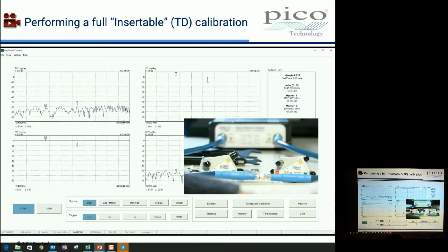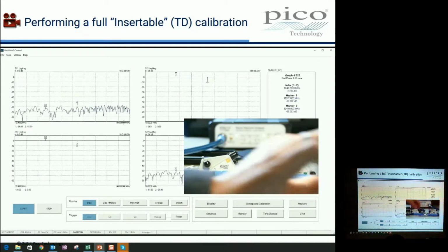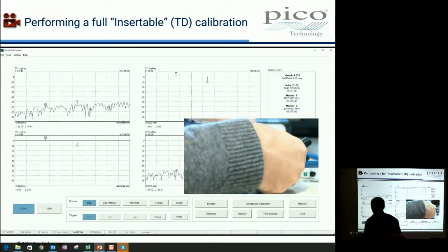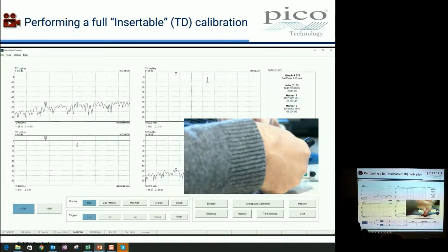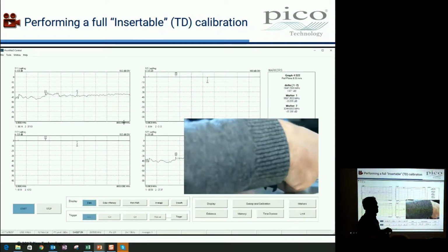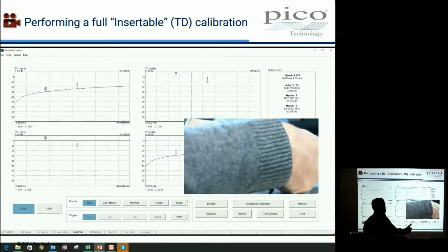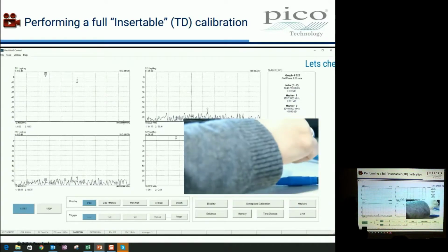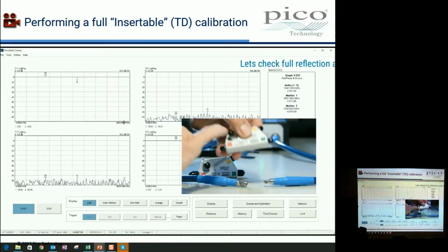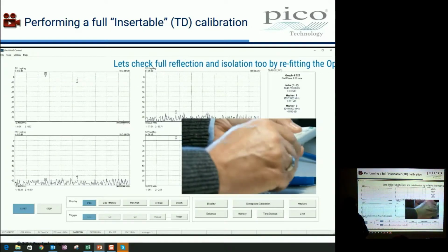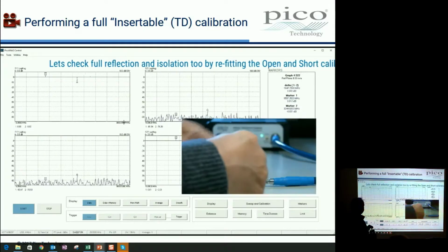This one is apply calibration. It's a big step applying the calibration. It's a point at which you're pretty happy that you've done things right here. You are going to get a chance to check things out before you save everything utterly and completely. But yes, so two different applies for two different reasons.